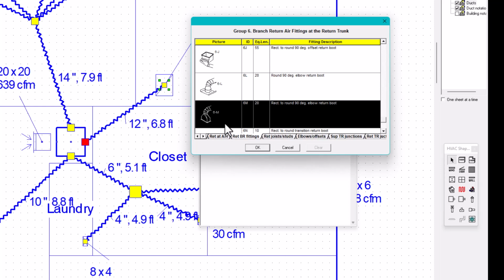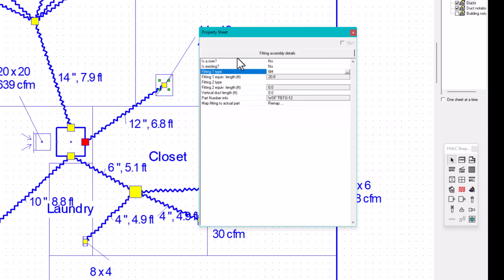So you calculate two things. Number one, you calculate the pressure loss based on this, and then you put the same pressure loss in a straight duct, and that's the equivalent length. So if we put in a duct of 20 feet, that could be equivalent to the same pressure loss of this arrangement. So that's equivalent length, it is not effective length, right? After the explanation, we're going to go to the other equivalent length and check.